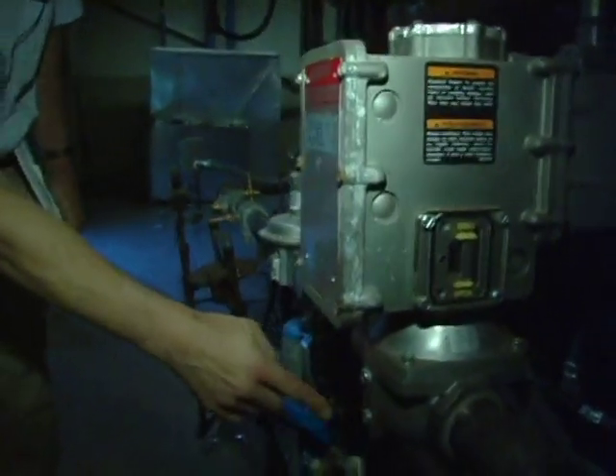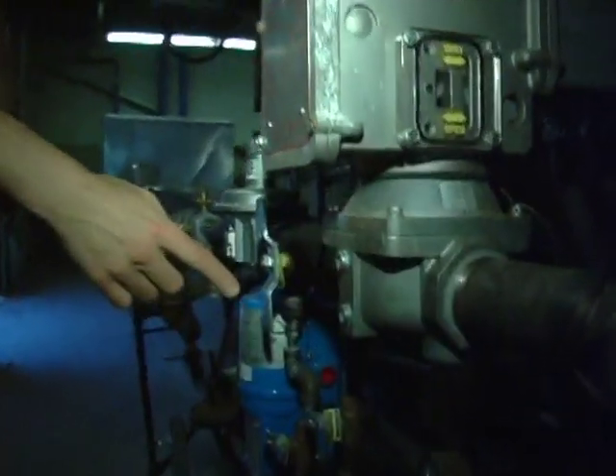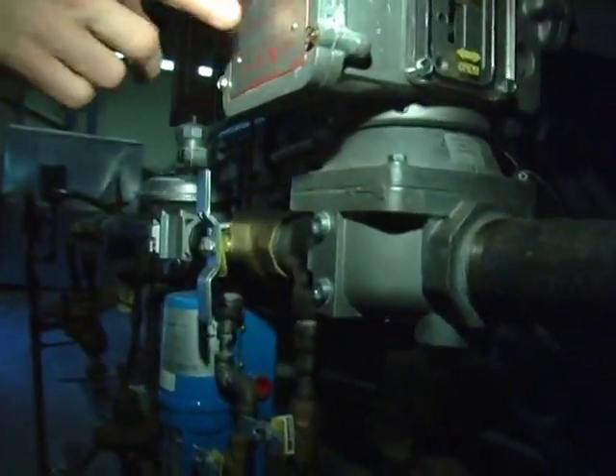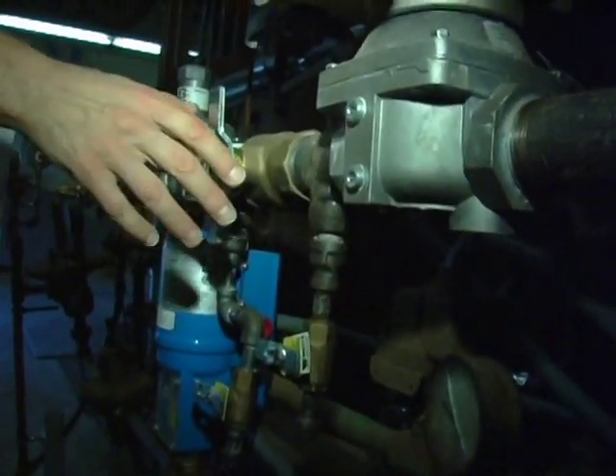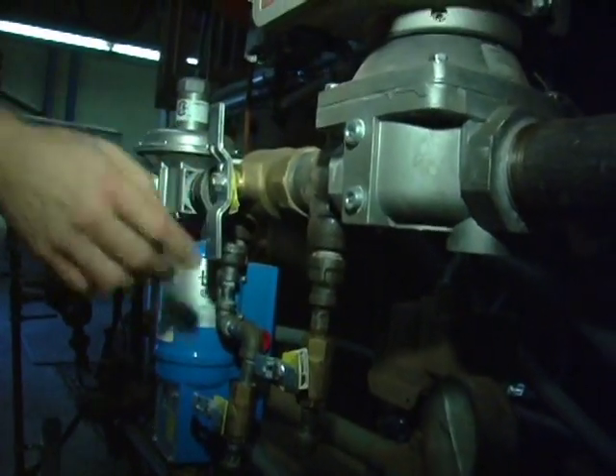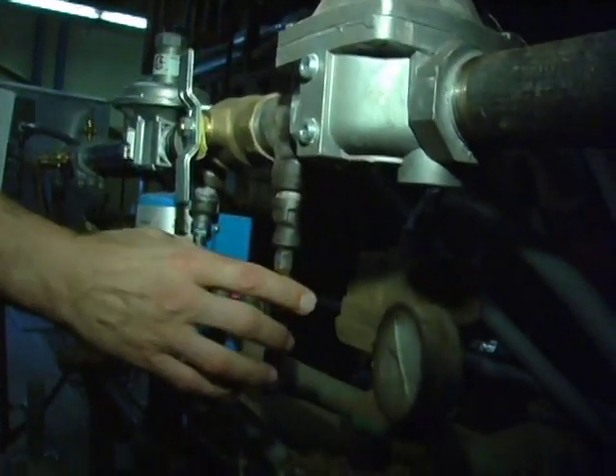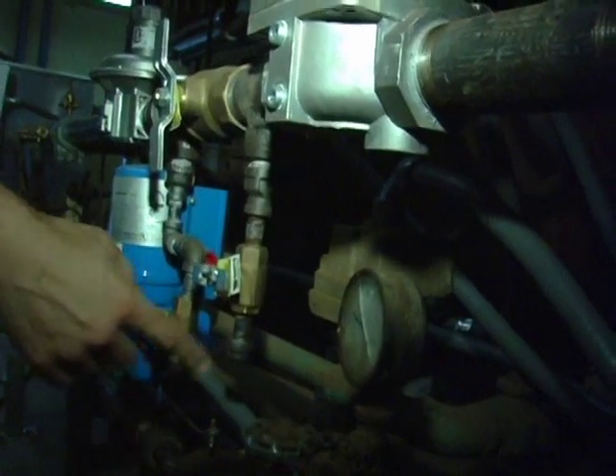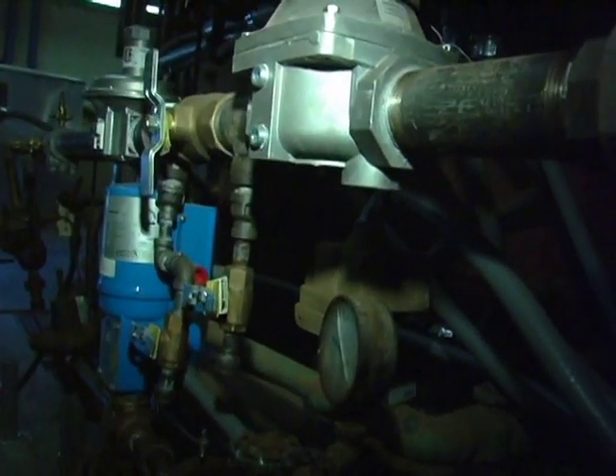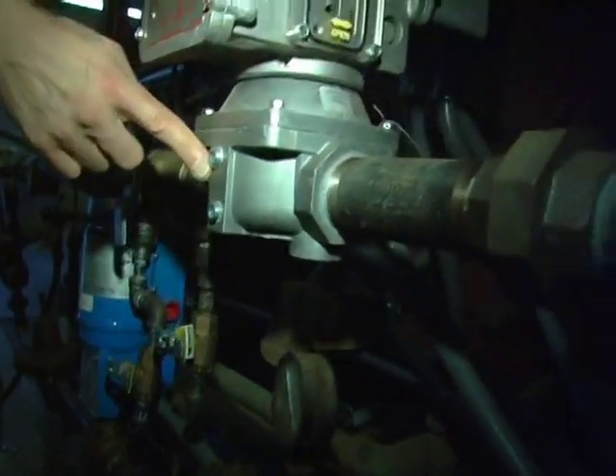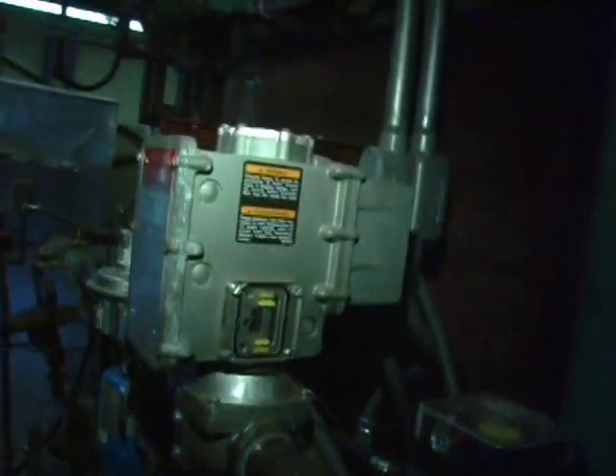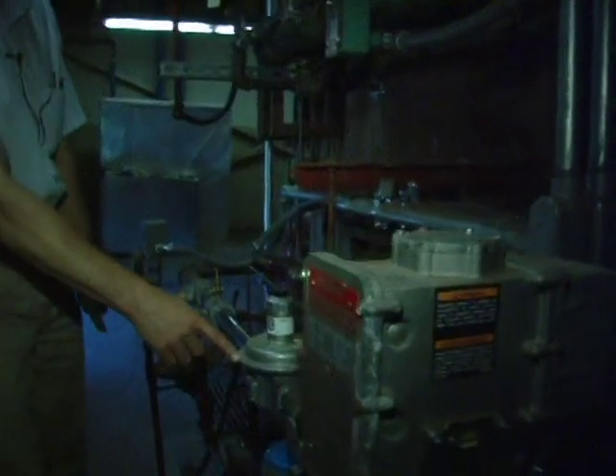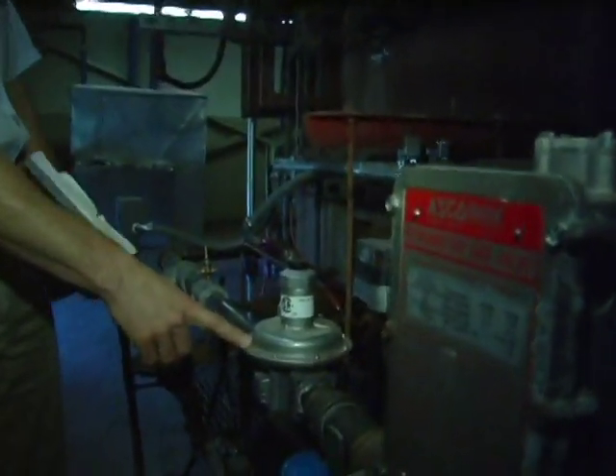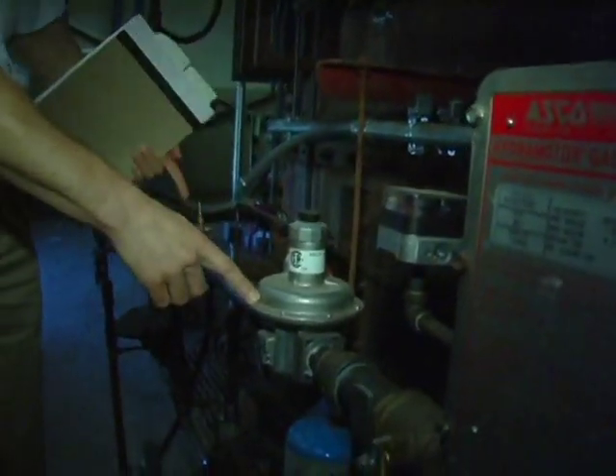You notice you've got these taps here. These leak test ports are for checking whether or not this valve is working. You would close this. It's closed now. You'd put a glass full of water here, open this up, and see if you had any gas coming out of there to check to see if this was fully closed. You know, that's leak test. This is the regulator. This modulates the amount of gas that's coming through that you're going to fire.